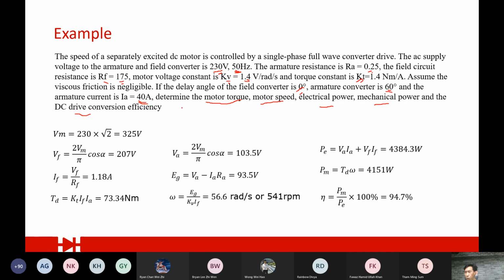To do that, first we find the peak voltage: 230 multiplied by square root of 2 gives 325. Then we calculate the field voltage by applying this equation, with cos at 0 degrees, giving around 207 volts applied to the field.